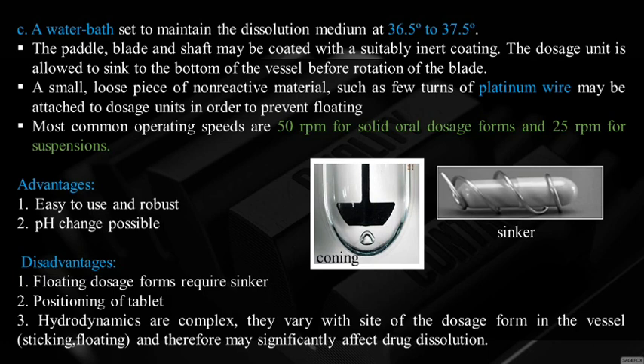Advantage: easy to use and robust; pH changes are possible. Disadvantages: floating dosage forms require sinkers. Positioning of the tablet is also important. Hydrodynamics are complex and vary with the site of the dosage form in the vessel, which may significantly affect drug dissolution.